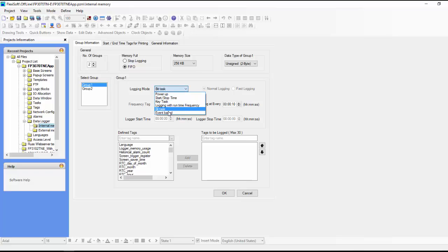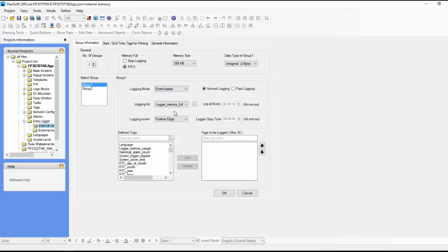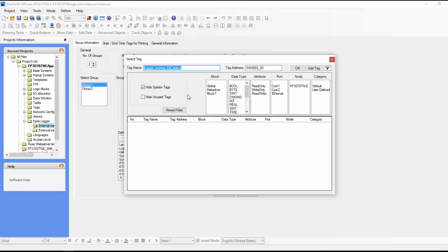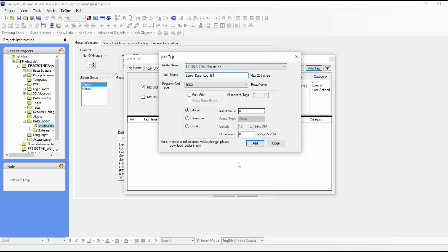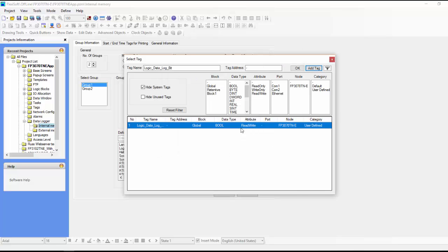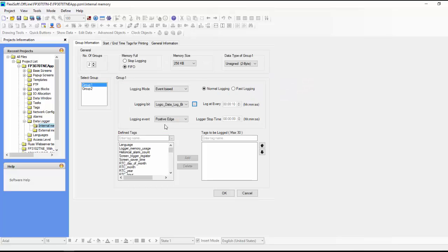The most common one that we see and that we use is the event based. And so here we can define what the logging bit is. So we can create a new tag here, a new boolean tag. And so we just say add tag. And we can say it's a boolean and we can just say logic data log bit, something like that. So now we can choose that. So close this, we're going to select this tag.